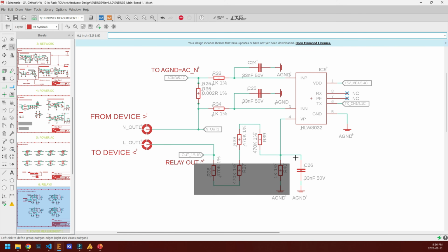Voltage is measured through the VP input using a high value divider. The top leg is 4 470 kΩ resistors in series, 1.88 megaohm in total. The bottom resistor is a 1 kΩ to ground. That gives a divider ratio of about 1880 to 1. At 230 volts, VP is 230 divided by 1880, which is 122 mV RMS. At 120 volts, this value is 64 millivolts. The full-scale input voltage limit is plus minus 495 millivolts RMS, so the voltage sense is well inside the range.